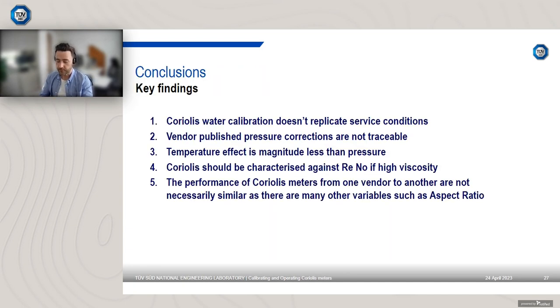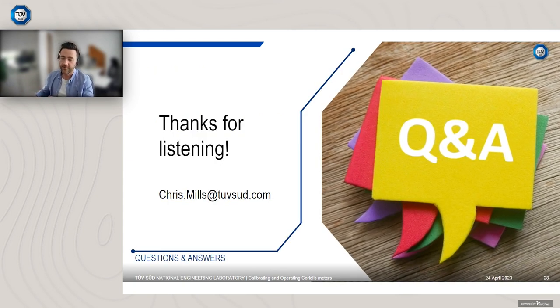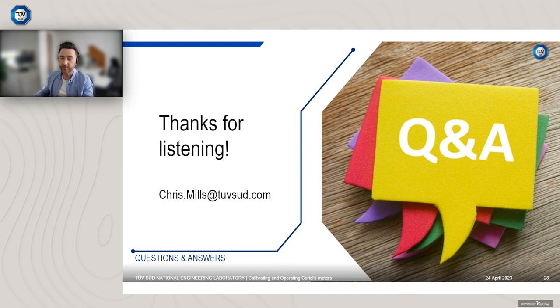And this one's critical. So people often think of a device as all being the same. So an ultrasonic meter performs like this, a Coriolis meter performs like that, turbine meter performs like this. However, what we find is Coriolis meters are different depending on the manufacturer, depending on the meter size, depending on that aspect ratio, but crucially depending upon the amount of research the manufacturer has conducted. So different manufacturers will have conducted a different amount of research at facilities such as NEL's with our high viscosity fluid or with our pressure EPAT facility at elevated pressure and temperature. So not all Coriolis meters perform the same. Ultimately, if you're purchasing a Coriolis meter for your application, you really want to then take it to a traceable flow laboratory to ascertain the performance.